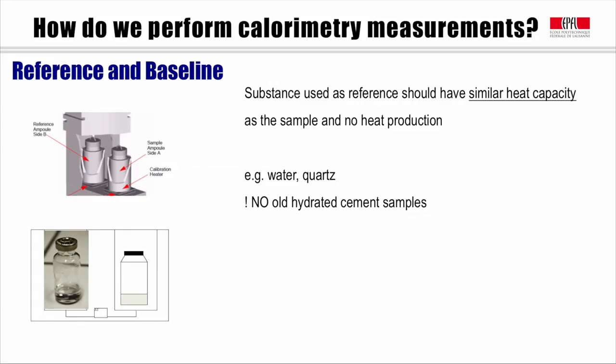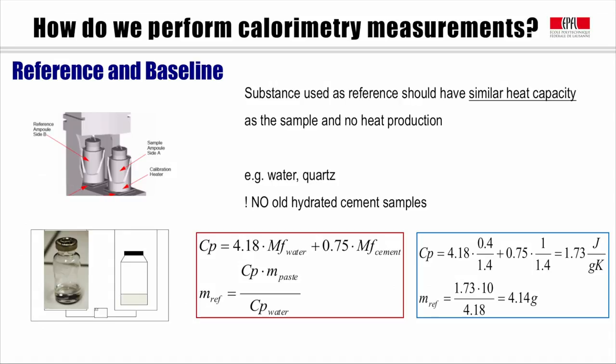To ensure a stable baseline and reduce background noise, the sample and reference ampoule should have the same thermal response. This is the rule for calculating the mass of the reference. Here is an example of calculating a reference for 10 grams of cement paste with water-to-cement ratio of 0.4. By knowing the specific heat capacity of water and cement powder, the mass of the reference can be calculated.